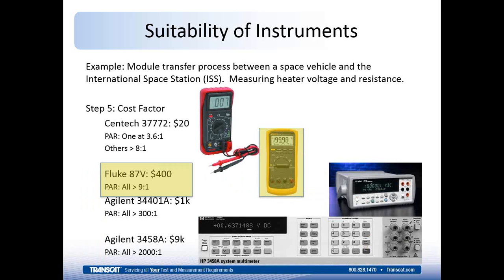And then finally, the cost factor comes into play. So here we have each of the instruments we're considering. We can see that with the Centech 37772, it's a very low-cost item, it's 20 bucks. There is one PAR that's at less than 4 to 1, and the others are greater than 8 to 1. So that needs to be considered, whether that's going to be a risk down the road or if that can be used universally. The Fluke 87V is a $400 instrument, but it has very good tolerances on it and gives process accuracy ratios of better than 9 to 1 across the board.